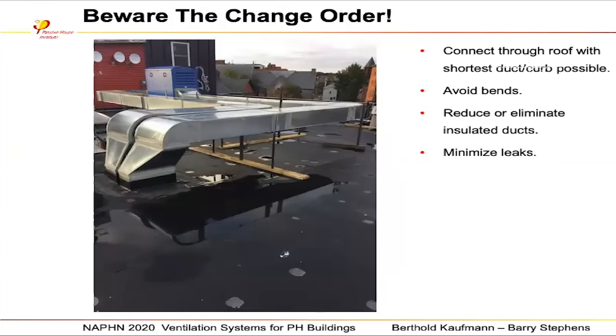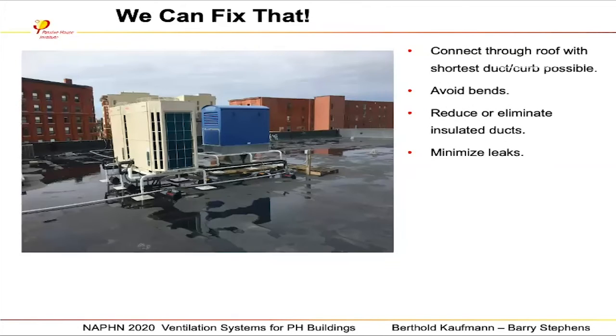This is another project that's got about 30 feet of ductwork on the roof from where the unit is on an old curb over here going to the penetration through the roof here. We were able to fix this. I'd liken this to a Prius. We've got a Passive House certified HRV on the roof, and then we hook a 20,000-pound trailer to it and we expect 50 miles to a gallon. It just isn't going to work. We fixed that, and that's what it looks like now. So we put it on a stand and we put it right where the penetrations are, and this curb and ducting is insulated going directly into the building. We eliminated the problem there.